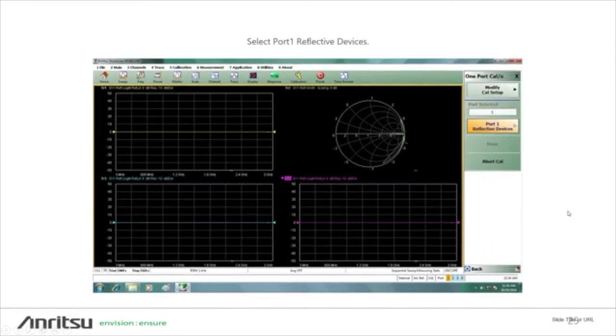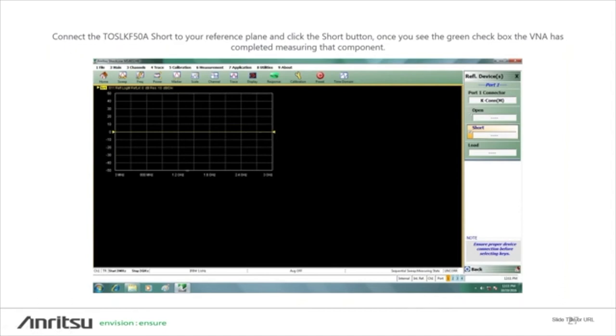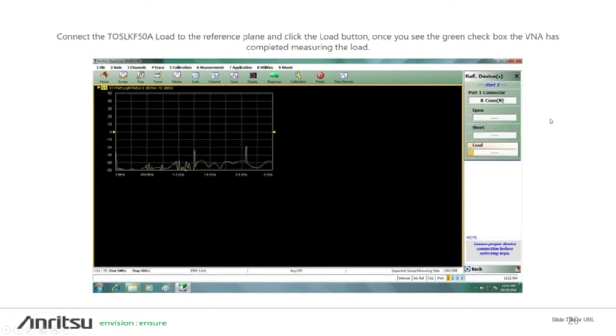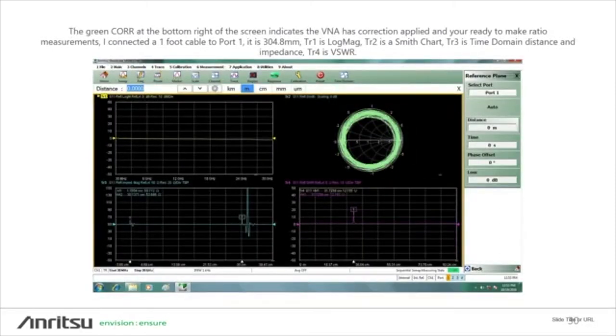We're going to do a manual one-port calibration. We can modify the cal setup, and when we select Port 1 devices, we connect our open. Once the open is measured, you'll see a green checkbox. Then we connect the short and select short — again, a green checkbox appears. Then we connect our load; once finished, another green checkbox. After that, click Done, the calibration is applied, and we connect our device to perform a measurement.